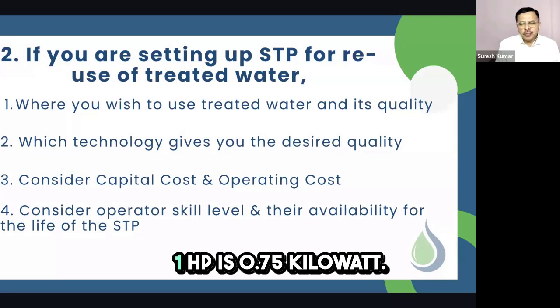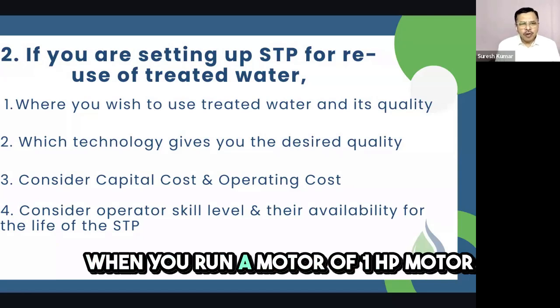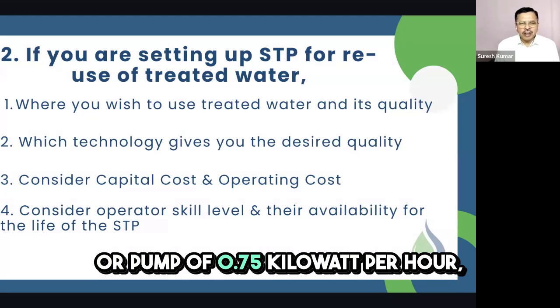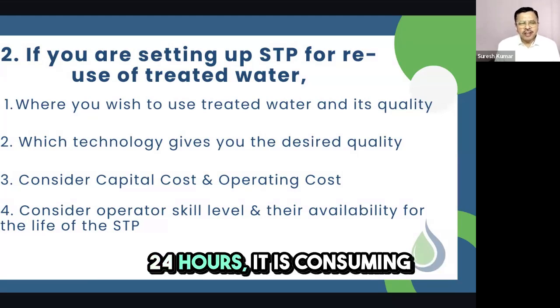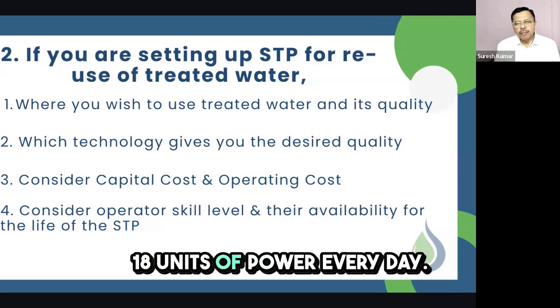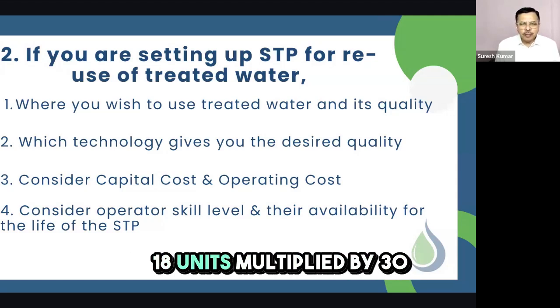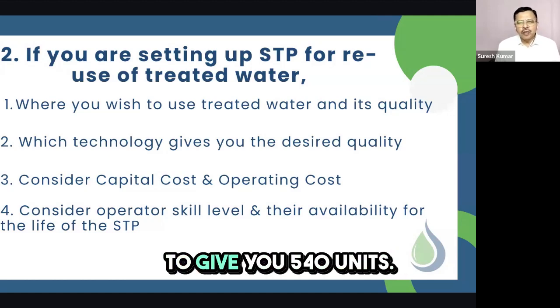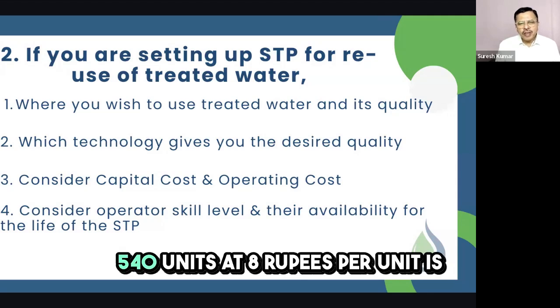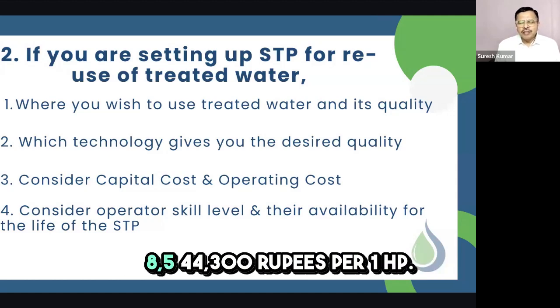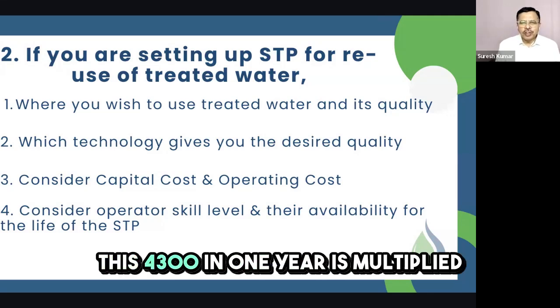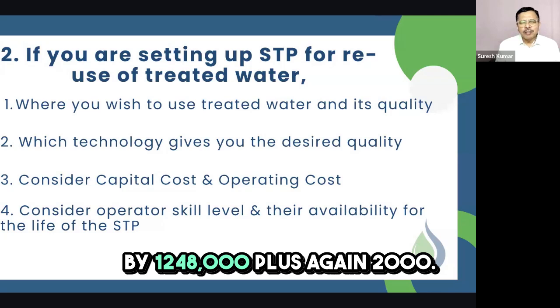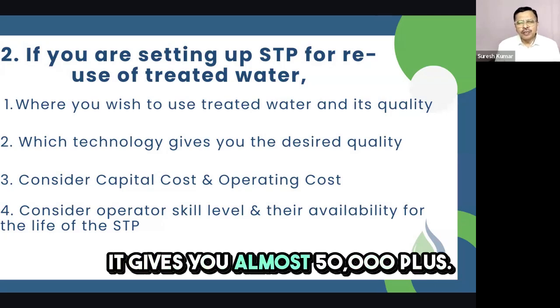Then 1 HP of power costs 50,000 rupees per annum. Here's how: 1 HP is 0.75 kilowatts. Running a 1 HP motor for 24 hours consumes 18 units of power per day. 18 units times 30 days gives 540 units per month. At 8 rupees per unit, that's about 4,300 rupees per HP per month, which multiplied by 12 months gives about 48,000 plus 2,000, almost 50,000 plus per year.